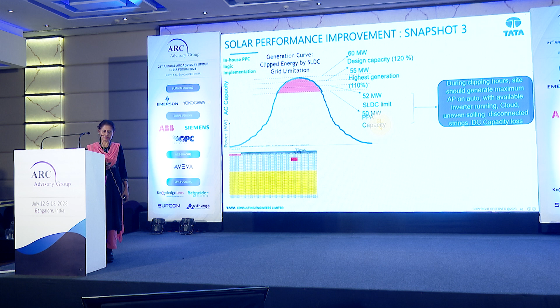In a normal set-point based system, there could be losses like soiling losses, transformer losses, or inverter problems. The automated power plant controller considers all these factors and gives a set point to the PPC to generate optimum power, so I don't lose anything. My generation is maintained between 48 and 52 megawatts, I earn more money, and there are fewer losses. Earlier, before implementing the PPC, there were a lot of disconnections happening in our plants.